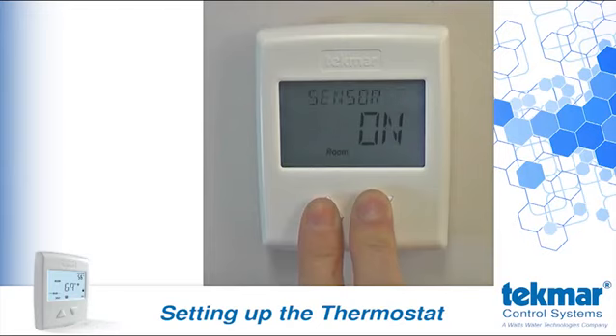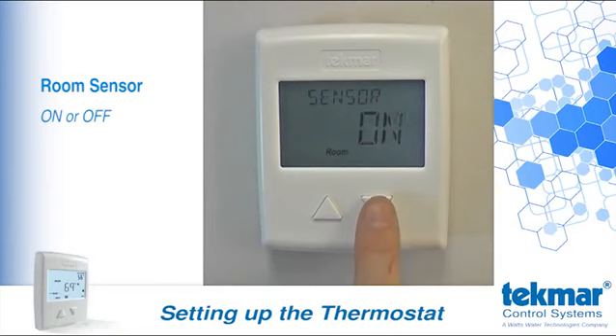The second setting allows you to enable or disable the built-in room sensor on the thermostat. In applications where you want the thermostat to operate based solely on the auxiliary sensor, then you can turn the built-in room sensor off. Examples of these types of applications include floor warming in bathrooms, or when thermostats are installed in the mechanical room with remote room sensors throughout the building. If you do want to use the built-in room sensor, make sure it is set to on.